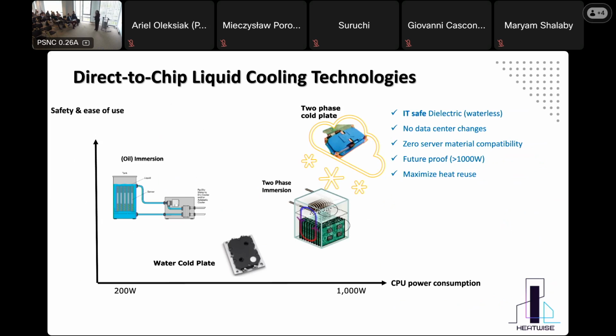The major drawback of the single-phase cold plate is that the liquid inside it is water or water glycol, meaning you bring water into the server. So in case of leakage, you put in danger a lot of money. When you're talking about AI servers, it's millions of dollars at risk.